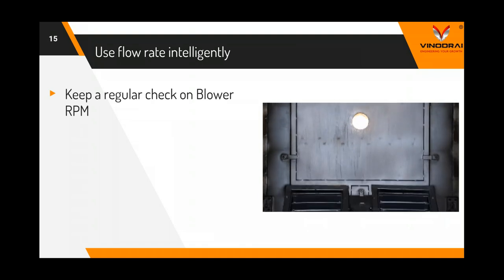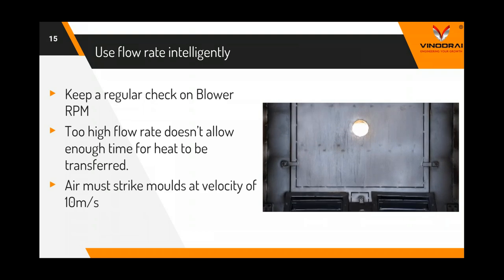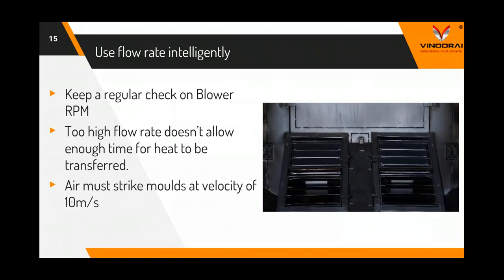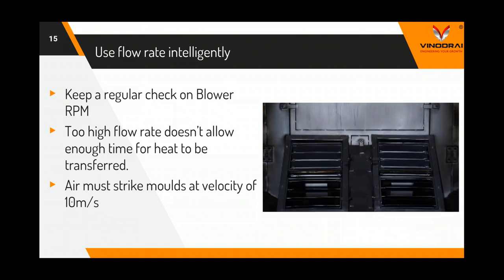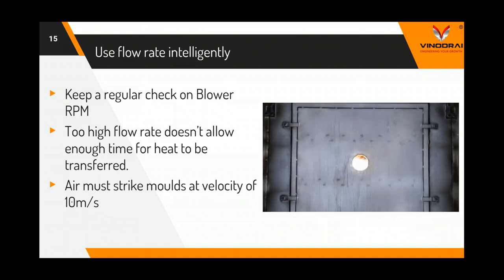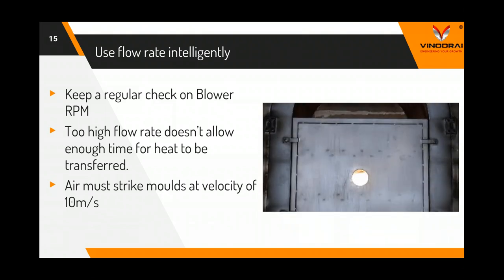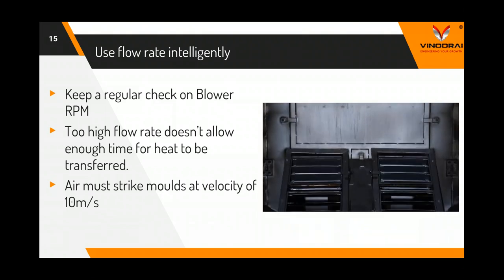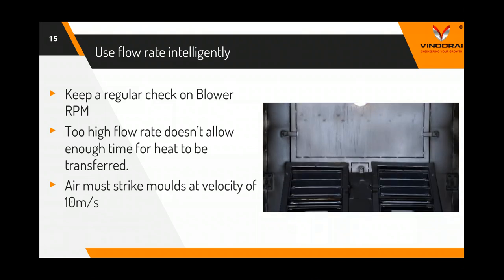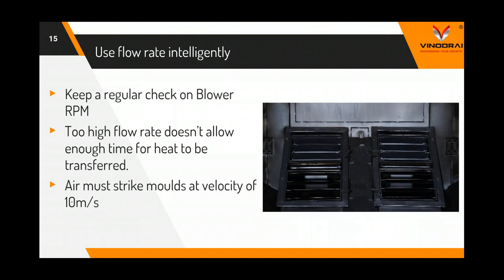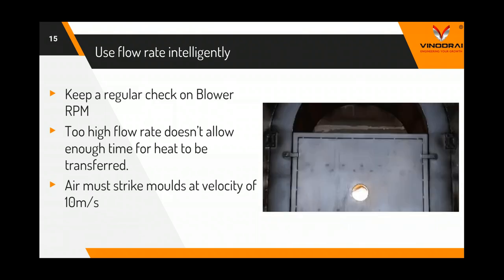All manufacturers have their own design considerations of CFM and RPM depending on furnace design. So make sure you consult your manufacturer and know the right RPM at which your blower should be running by design, and make sure that your blower is consistently at the right RPM and there's no clog in the impellers or something like that. This would give you good efficiency of your burner.